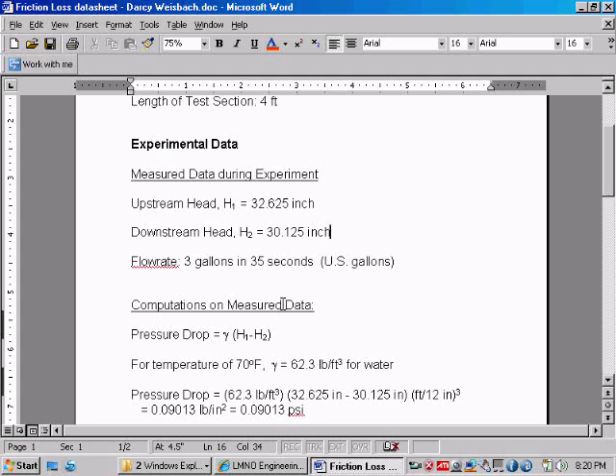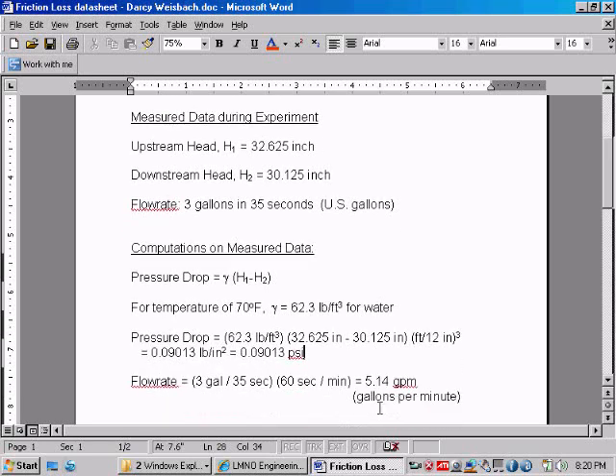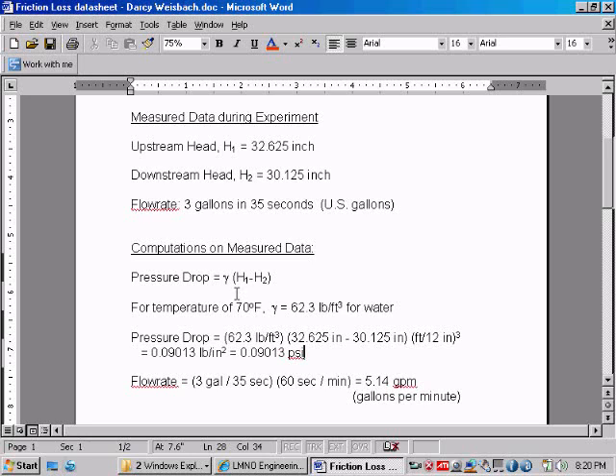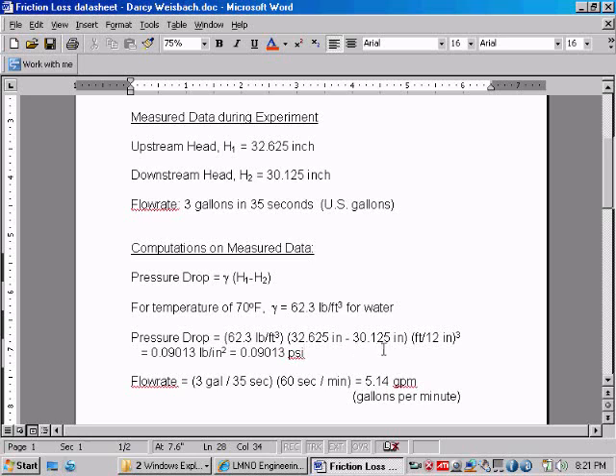But first we need to convert pressure drop into pounds per square inch to be used in our calculation. So the equation to convert head to pressure drop is gamma times H1 minus H2. Gamma is the weight density of water, which is 62.3 pound per cubic foot at 70 degrees Fahrenheit. Now, our pressure drop can then be computed as 62.3 pound per cubic foot times the head difference, 32.625 minus 30.125 inches times the unit conversion. And that gives us 0.09013 pound per square inch.